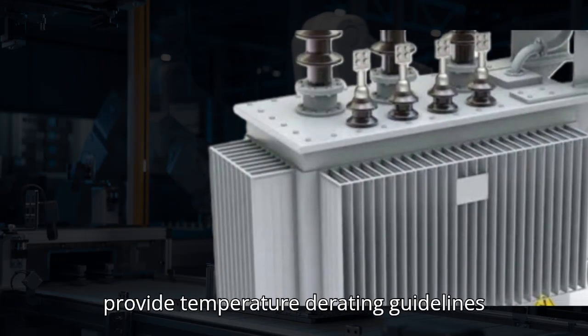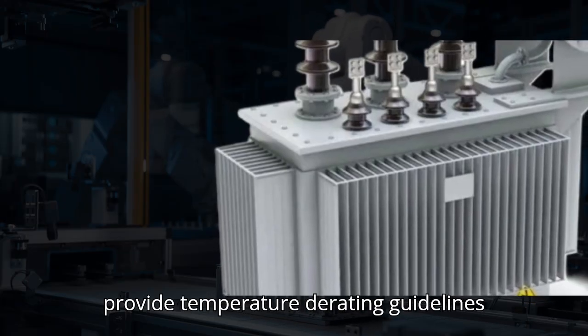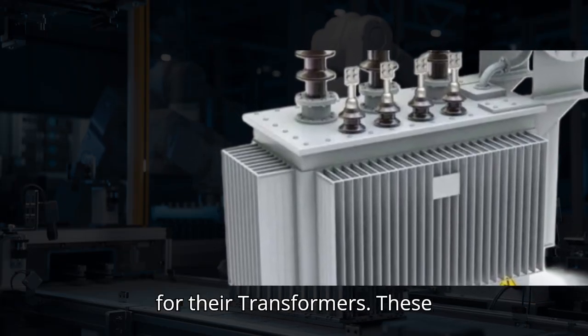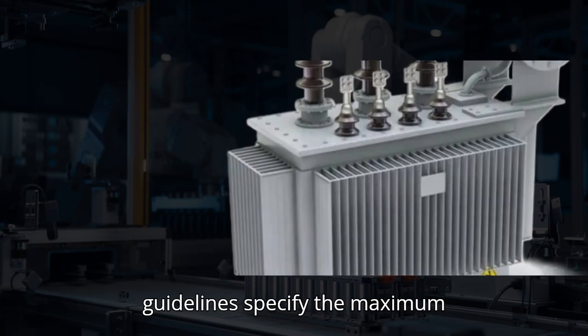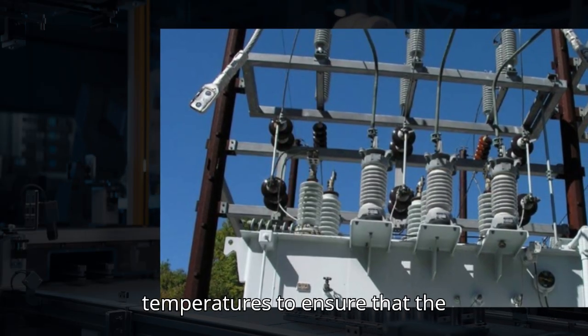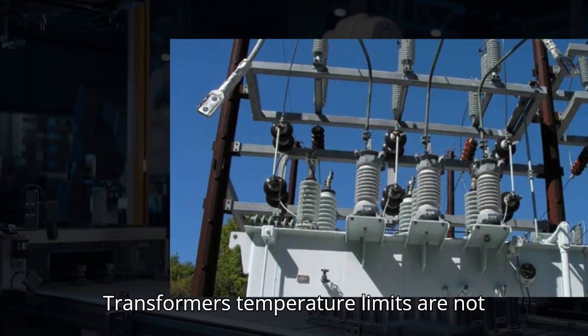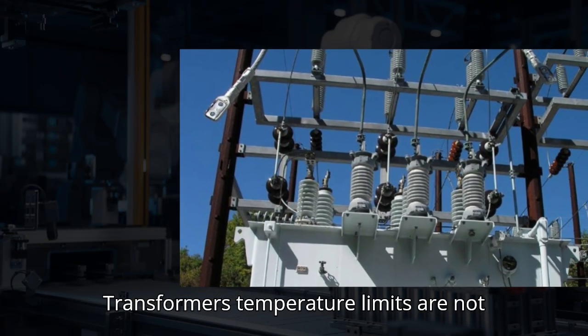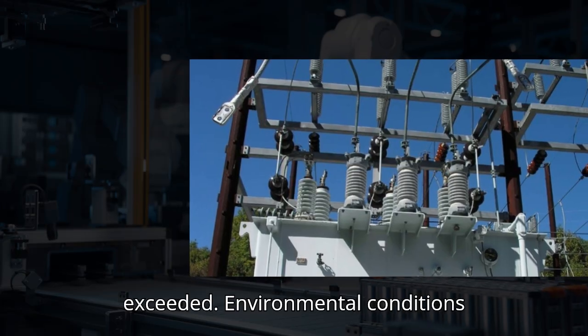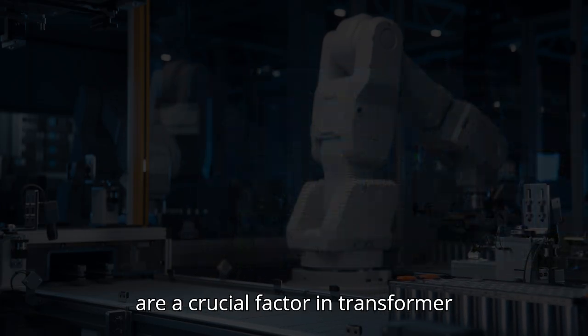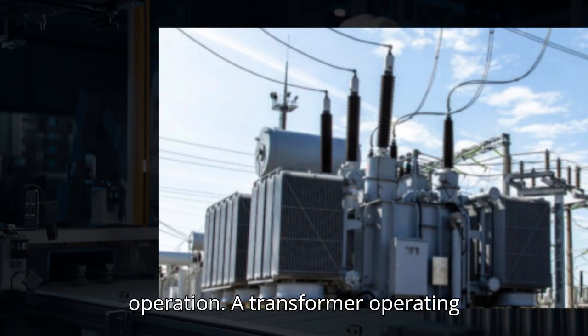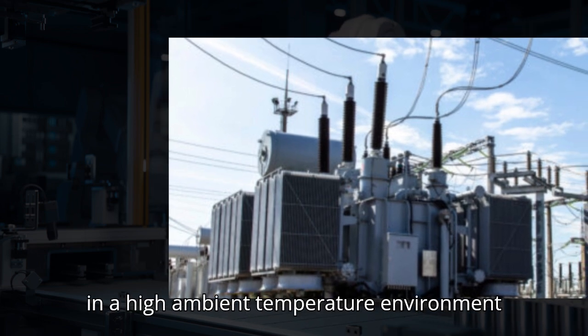To account for the impact of high ambient temperatures, manufacturers often provide temperature derating guidelines for their transformers. These guidelines specify the maximum permissible load at different ambient temperatures to ensure that the transformer's temperature limits are not exceeded. Environmental conditions are a crucial factor in transformer operation.